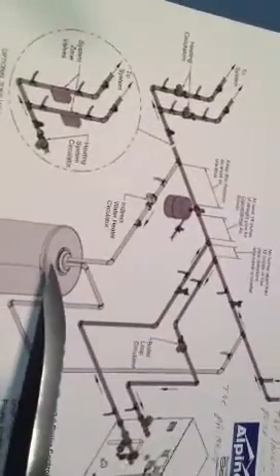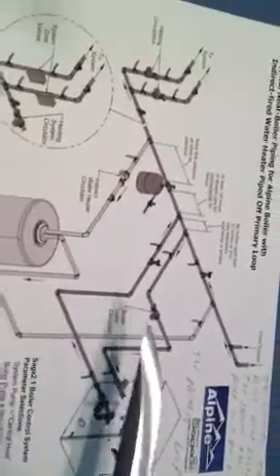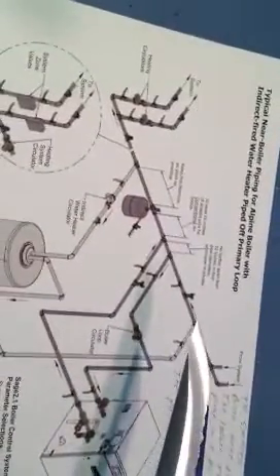If you were at a third zone there'd be a third circulator there and there'd be a third return there. This pipe is now your boiler water, and by the way this is the expansion tank and the cold water feeder valve. You even feed the cold water into this pipe. But watch what happens when I shake the white paper off to simply add a storage tank for domestic hot water to take a shower with. Now it's in gray so not to confuse you with the boiler water.